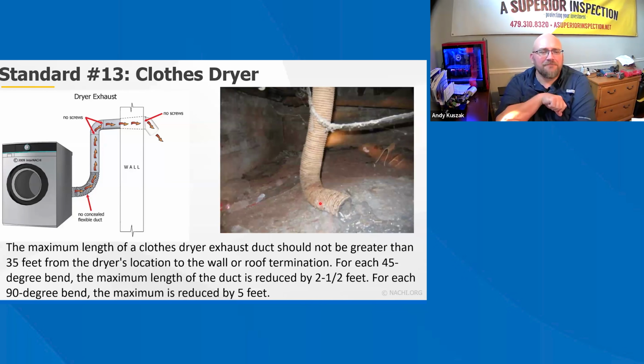Clothes dryers. All right, so clothes dryer exhausts pose a different problem compared to other exhaust systems because the air they carry is damp and infused with lint. The exhaust of a dryer must vent outside and not discharge into an attic or a crawl space because the wooden structural members could be affected. Exhaust vents should have a backdraft damper installed to prevent cold air, rain, snow, rodents, and pests from entering the vent. The length of the clothes dryer exhaust ensures that the dryer exhaust blower will be able to push sufficient air volume to take away damp air and lint.